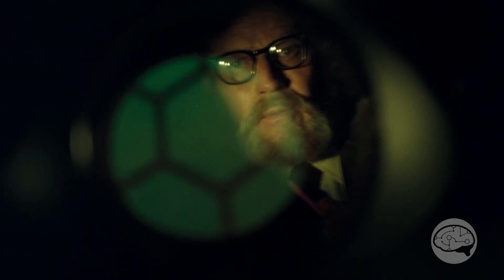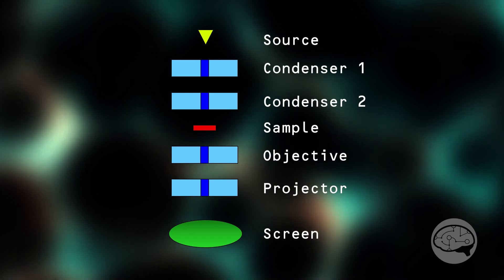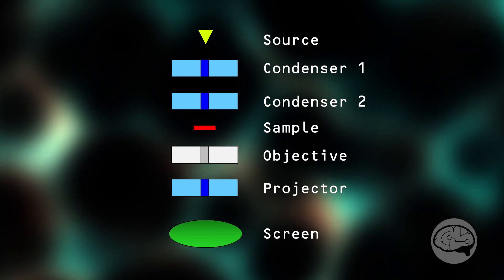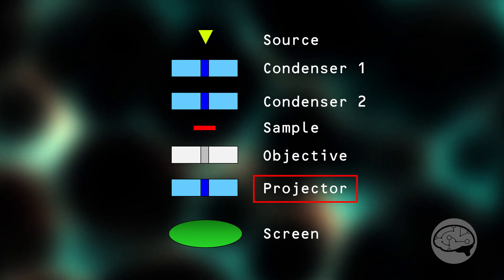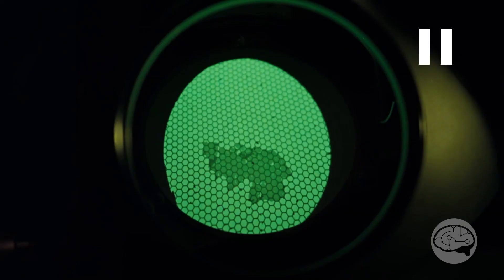So what's happening in the microscope to allow that? Well, it's pretty simple. In low mag mode the objective lens is either turned off or the current running through it is severely reduced. This allows you to go to a much lower magnification, and you'll instead use the intermediate and/or projector lens to focus. This destroys your resolution, but you're also not going to be able to go very high in magnification either, so it doesn't really matter.